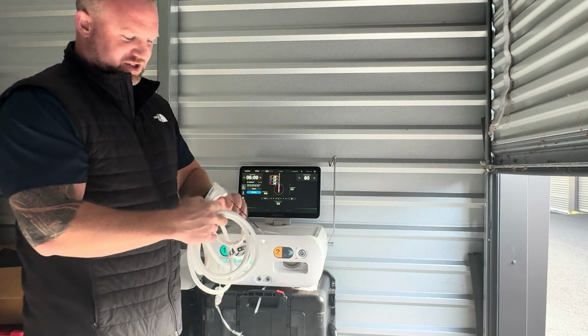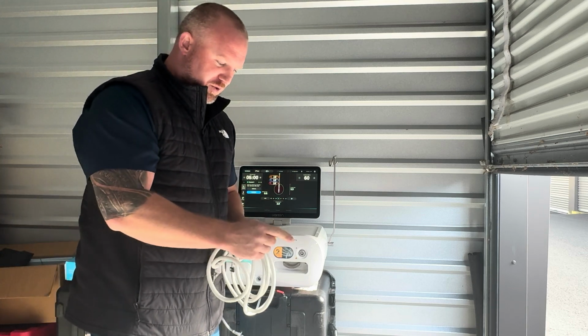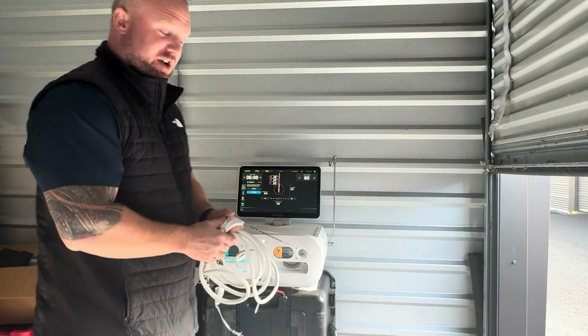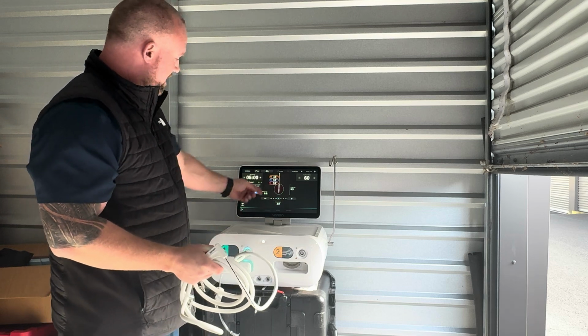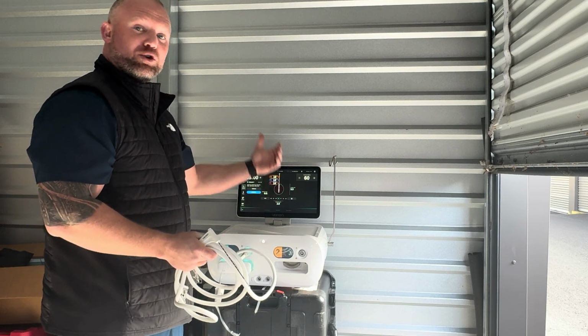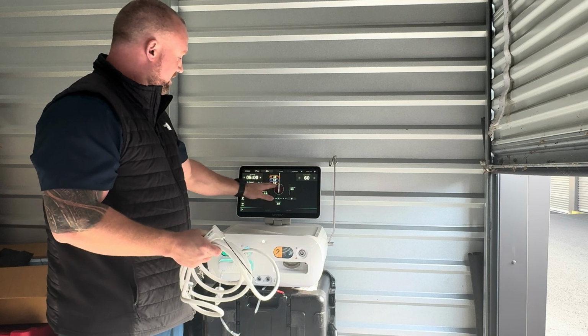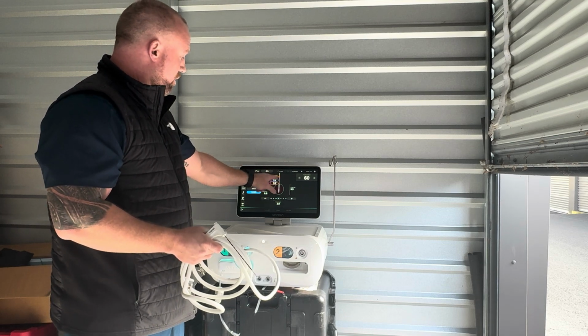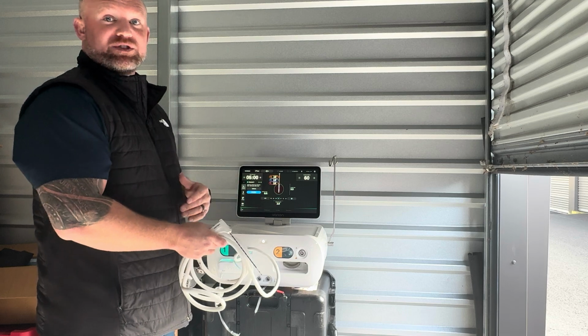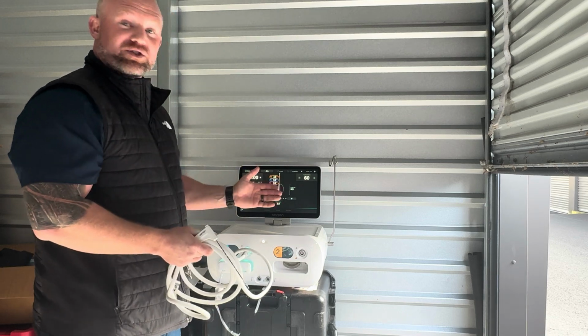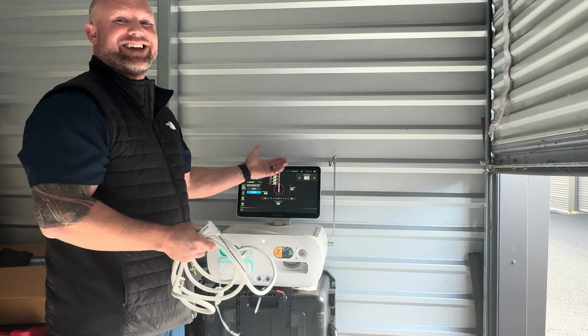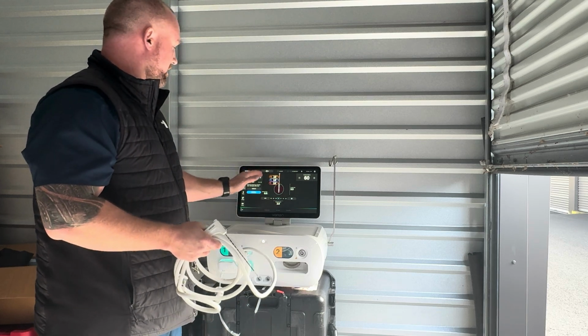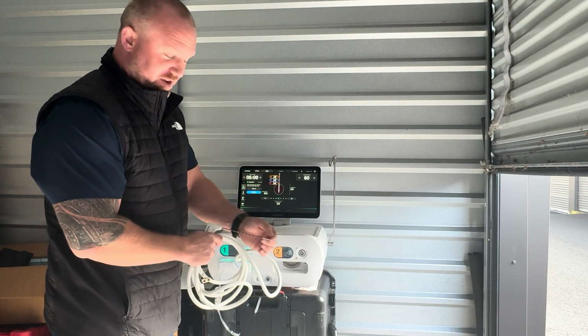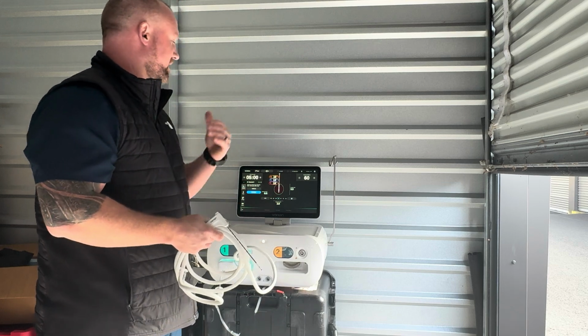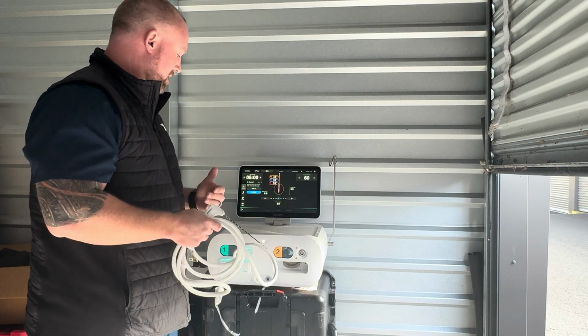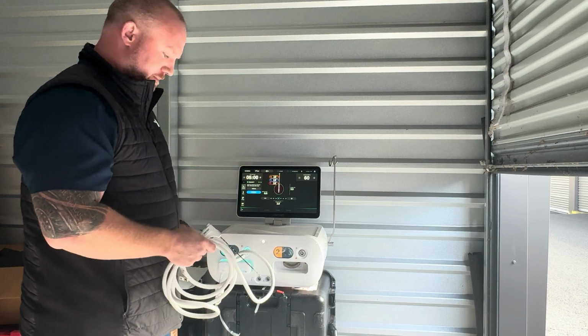When we're looking at the probe itself, we have multiple markings that are going to correlate to what's on here. So as you saw when we plug this in, these thermocouple temperature sensors illuminated, and it's giving us 3 active readings at 3, 4, and 5 centimeters up the probe shaft, which is going to allow us to know if we're next to any critical structures, and we can watch to see if those critical structures are heating up. So it's a great little piece of technology that they input along this actual shaft to give us more information, to keep the patient safer, and to keep it to have a much better ablation in the long run.